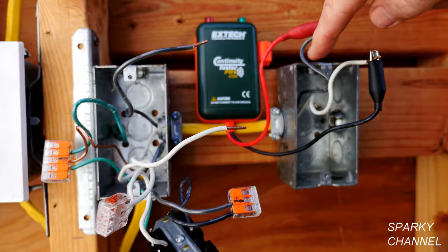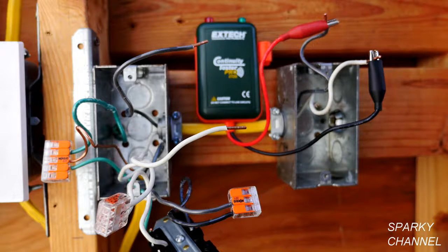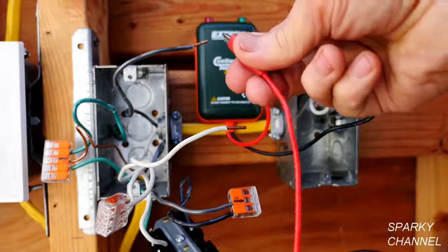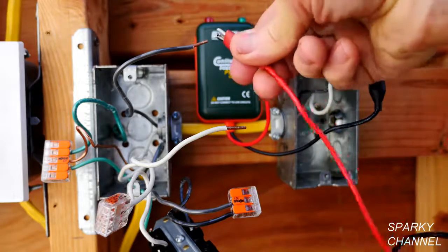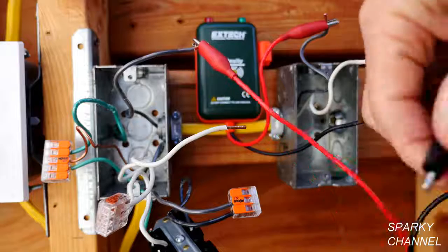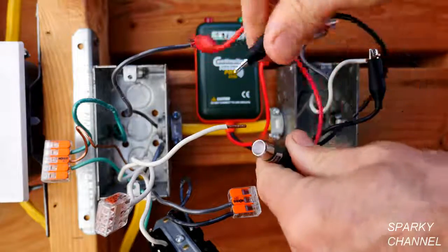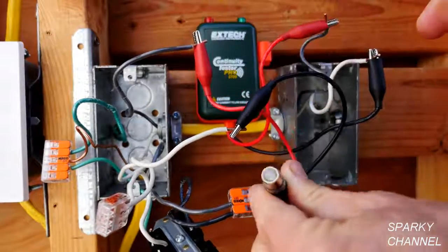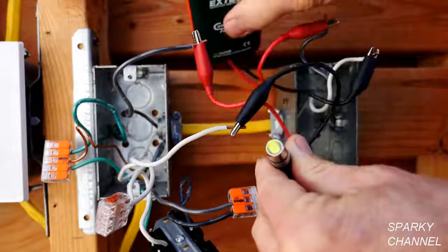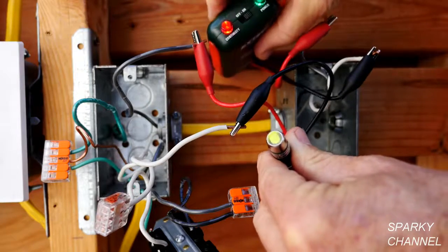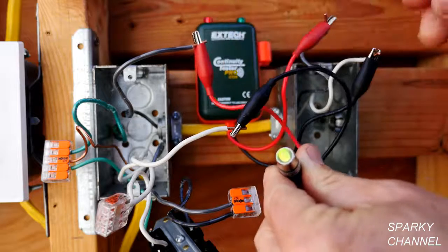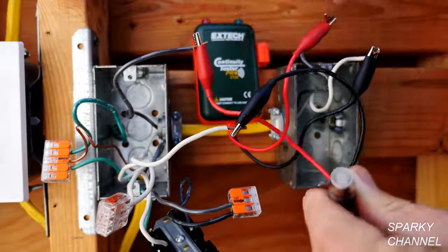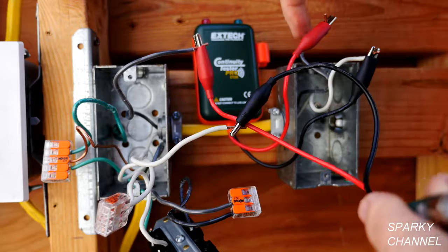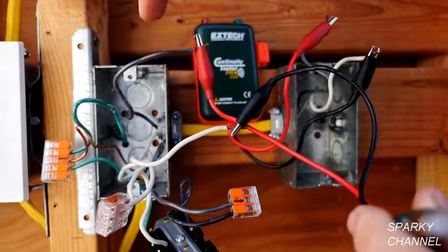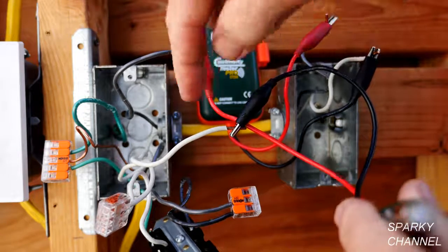And we can actually test both sets of wires simultaneously with this tester, which is a really nice feature of it. So I'll put, just as I did over here, I'll put the red on the black wire and I'll put the black on the white wire. And you see, it is saying continuity. So this black hot wire is this black hot wire, and this white neutral is this white neutral.